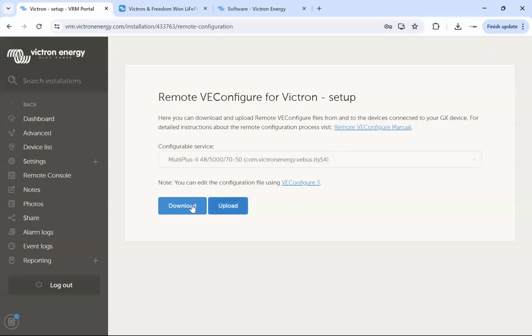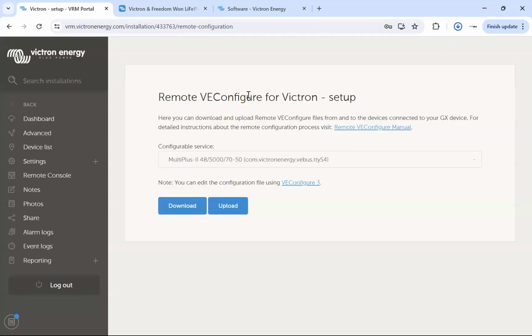Now, what I do like to do is I actually like to download that again. This is a little bit pedantic, but it's good to download it again, because that means you can go through and check that all the settings have taken, and there's no settings in that program that haven't taken. There might have been an internet outage during the upload, or it could have been anything like someone turned on a crazy noisy load, which is unlikely, but it could be something like an old VSD that's putting out a lot of harmonics, and the inverter may not have taken that program.